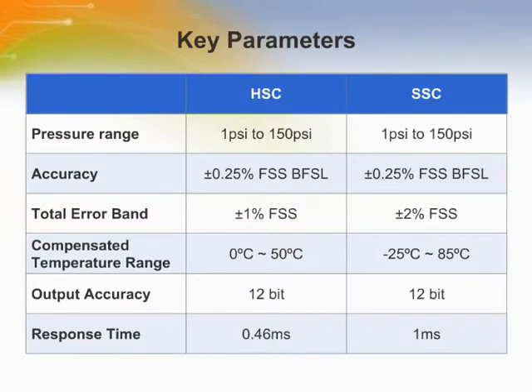Here are some key parameters to help you roughly evaluate these sensors. Both series look similar, but the total error band, compensated temperature range, and response time is slightly different. The compensated temperature range is the temperature range over which the sensor will produce an output proportional to pressure within the specified performance limits. Obviously, SSC series has wider range.